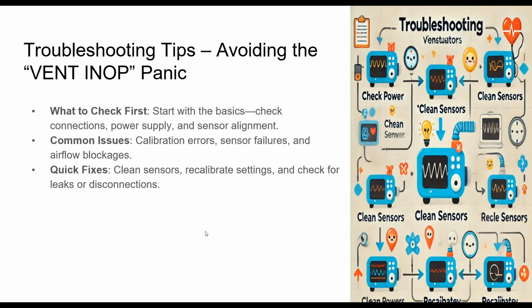There are some common issues that I'd like to talk about. Some of the common issues are calibration errors, not typically from what I've seen with biomedical technicians doing something wrong and then putting it up on the floor. But what I refer to as calibration issues is sometimes there are use errors and somebody has calibrated the device not knowing that they've calibrated it incorrectly, or not knowing that they were even in a calibration related setting and calibrated it and then put it on a patient.